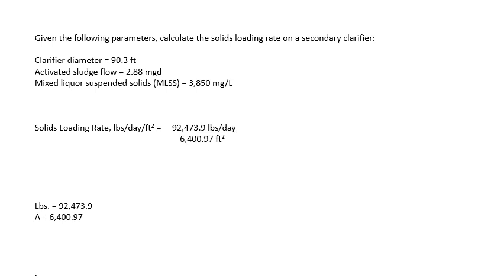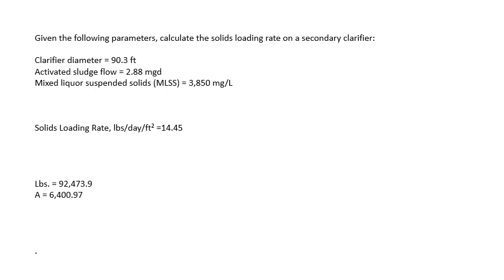So we plug these numbers into our solids loading rate formula, so 92,473.9 pounds per day divided by 6,400.97 square feet. And your answer is 14.45 pounds per day per square foot.